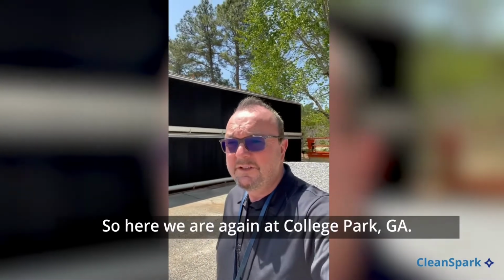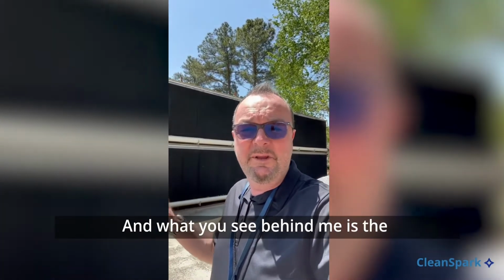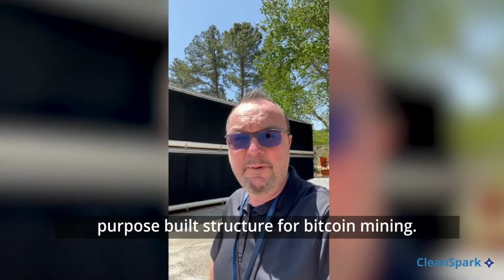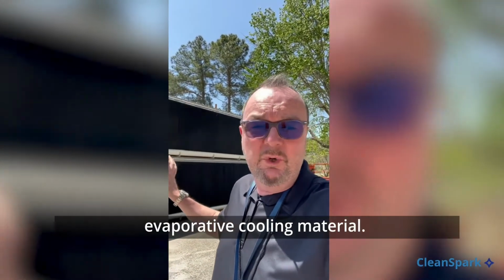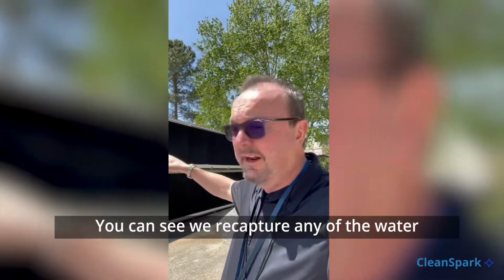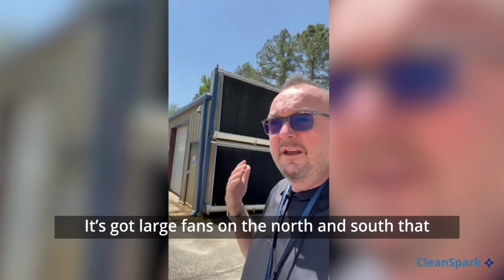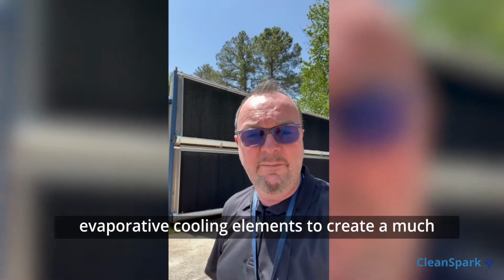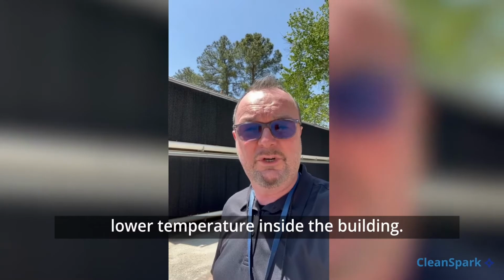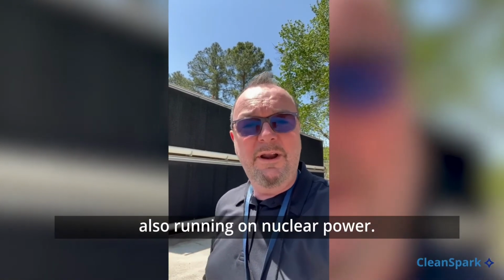Hey everyone. So here we are again at College Park, Georgia. And what you see behind me is a purpose-built structure for Bitcoin mining. The east and west walls are evaporative cooling material. And you can see we recapture any of the water and recirculate it. So it's pretty efficient that way. It's got large fans on the north and south that suck that air, the air through the evaporative cooling elements to create a much lower temperature inside the building. About 1,000 miners inside here, also operating on nuclear power.